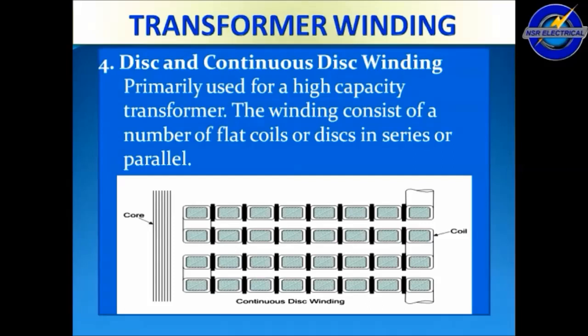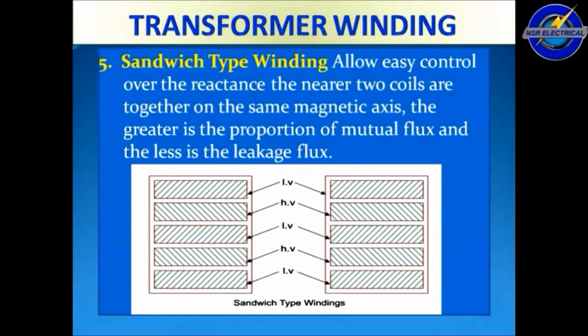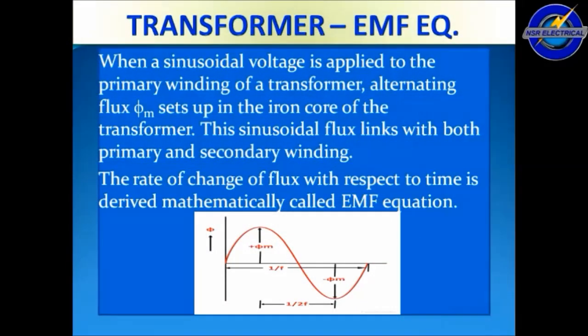The fourth one is disc and continuous disc winding, primarily used for high capacity transformers. The windings consist of a number of flat coils or disks in series or parallel. The fifth one is sandwich type winding, which allows easy control over reactance. When the nearest two coils are together on the same magnetic axis, the greater is the proportion of mutual flux and the less is the leakage flux.